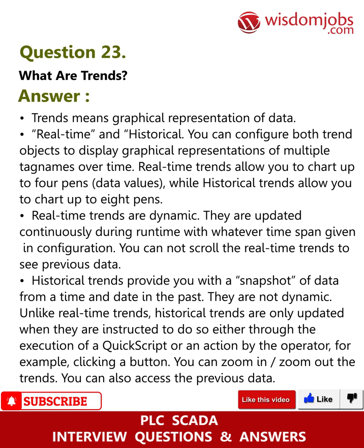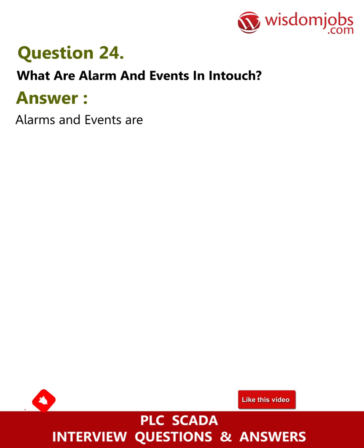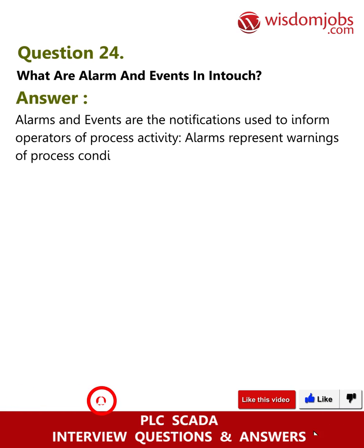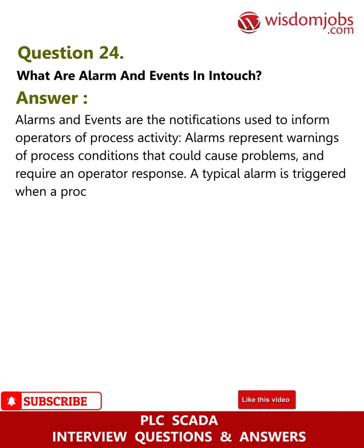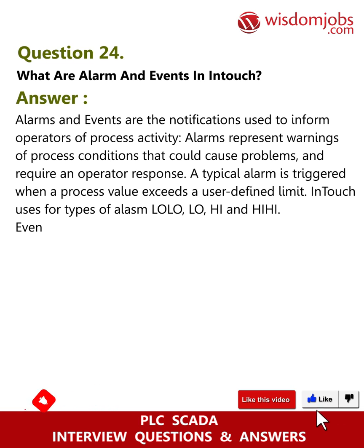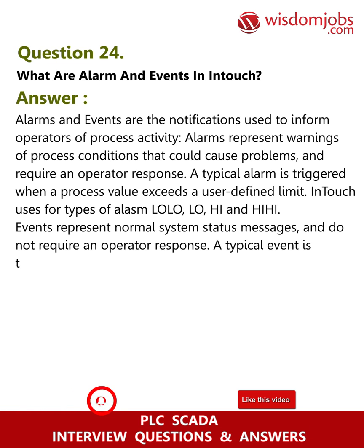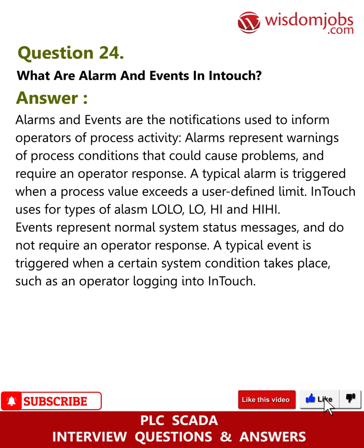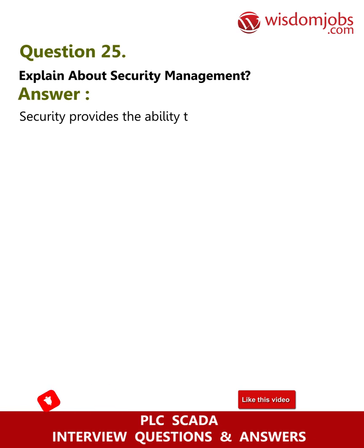Question 24: What are alarms and events in InTouch? Answer: Alarms and events are notifications used to inform operators of process activity. Alarms represent warnings of process conditions that could cause problems and require an operator response. A typical alarm is triggered when a process value exceeds a user-defined limit. InTouch uses four types of alarms: Low-Low, Low, High, and High-High. Events represent normal system status messages and do not require an operator response. A typical event is triggered when a certain system condition takes place, such as an operator logging into InTouch.